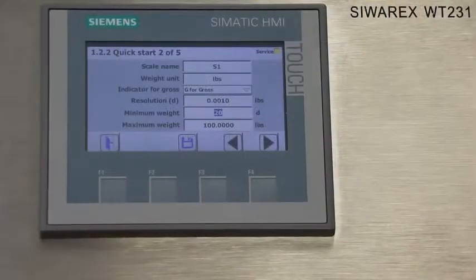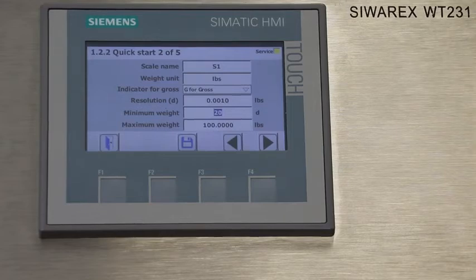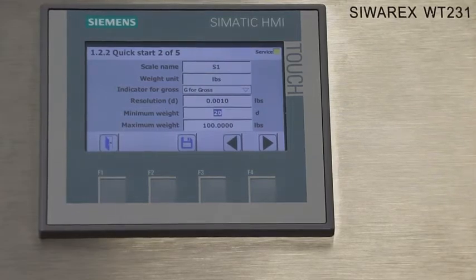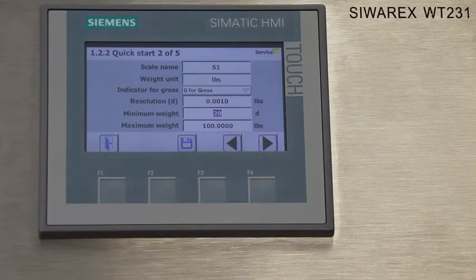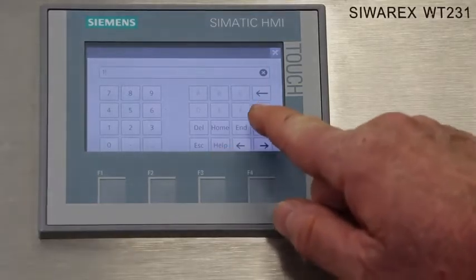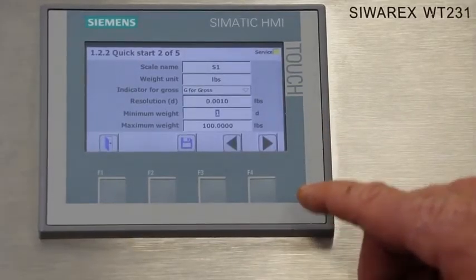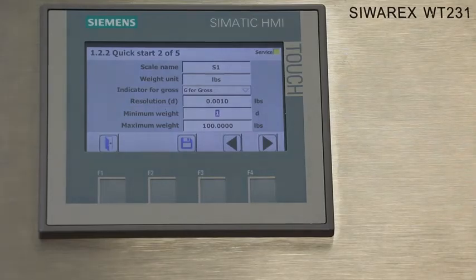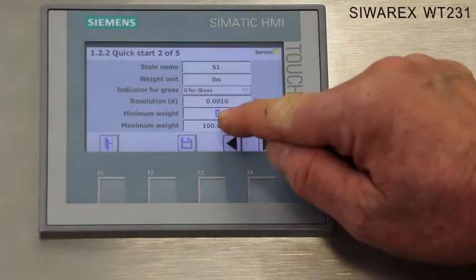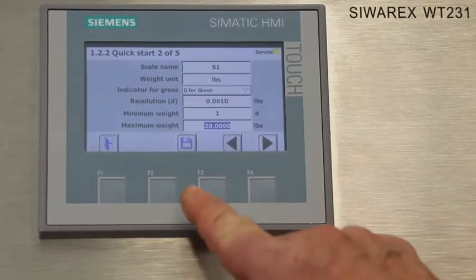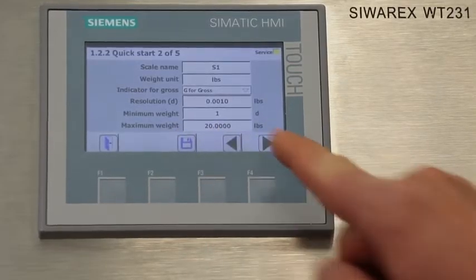The next field is the minimum weight value. This parameter is only used in custody transfer application. It's the minimum weight that could be used for a custody transfer. For this application, we're just going to enter a 1. In the next field is the maximum capacity of the scale. This is a 10 kilogram load cell, which converts to about 22 pounds. So we'll say the maximum capacity of the scale will be 20 pounds. We'll save these parameters and advance to the next screen.